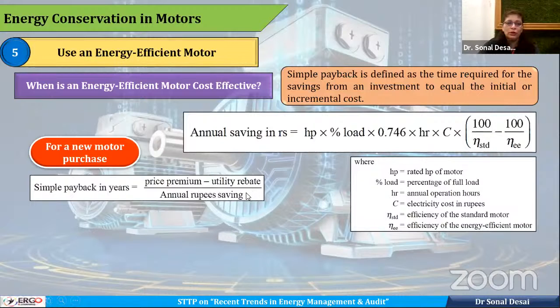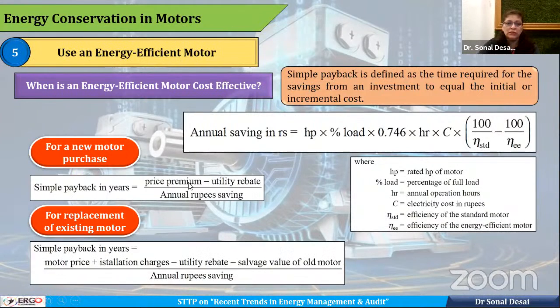So for a new motor, the annual saving is considered here. Price premium minus rebate, divided by annual saving, gives us the simple payback in years for a new installation. For a retrofit, we have to consider the motor price and the installation charge to replace the motor. We deduct the rebate available and the salvage, that is the cost of the old motor, and then divide by the annual saving to arrive at the value.